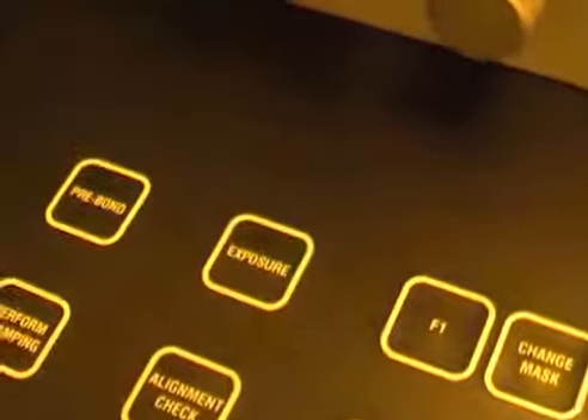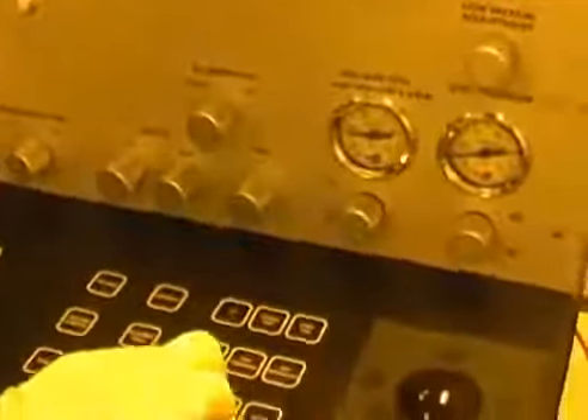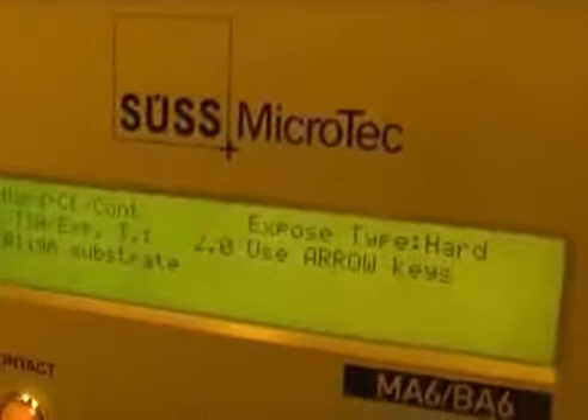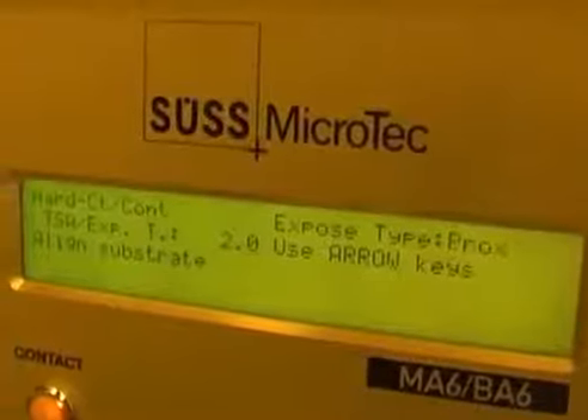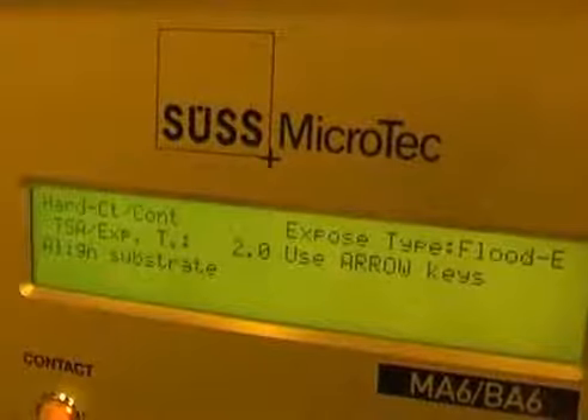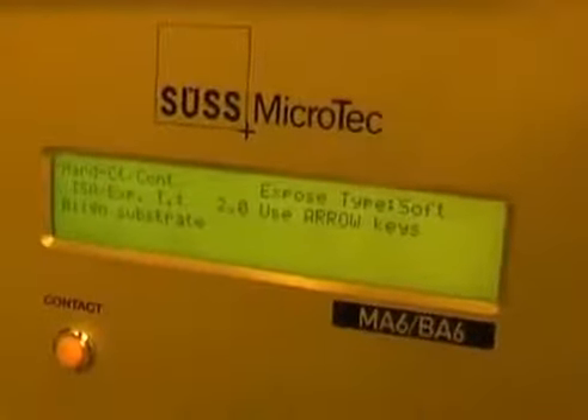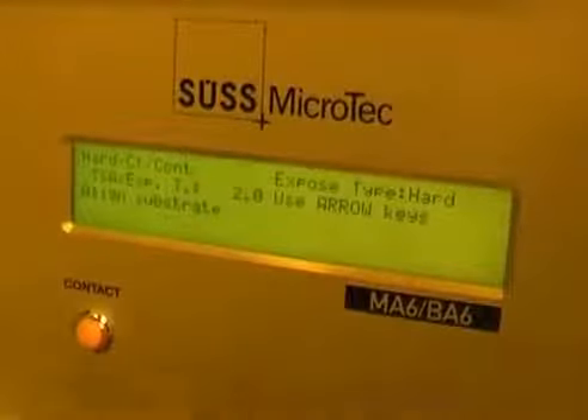But we must also consider what type of contact is required and the exposure time, depending on which photoresist we have used. To do this, we press select program, and we are now asked to use the arrow keys to scroll through our options: hard contact, low vacuum, vacuum, proximity and flood exposure. Also soft contact. For this job we'll choose hard contact. Once we've selected it using the arrows, we depress select program, and that stores the command.